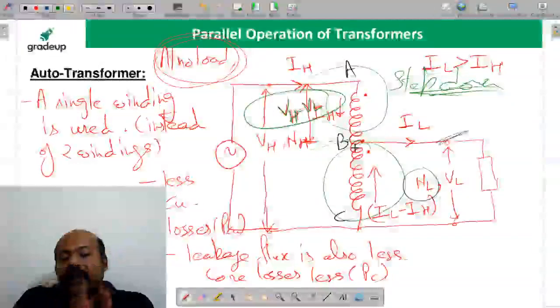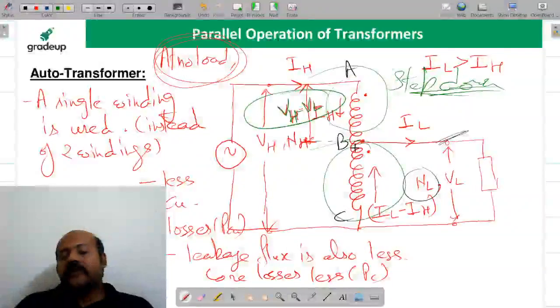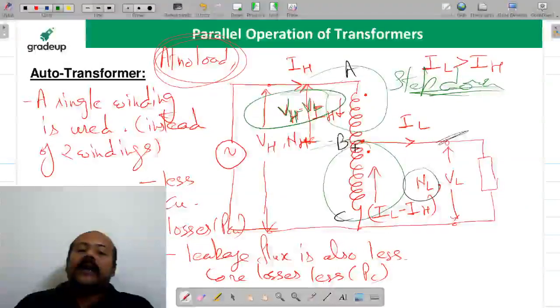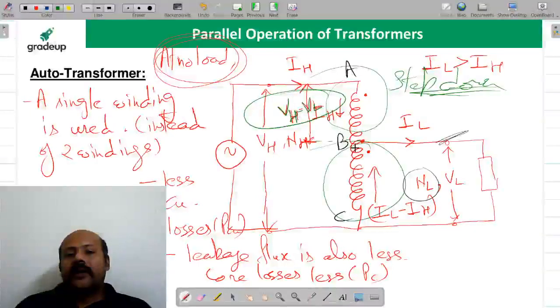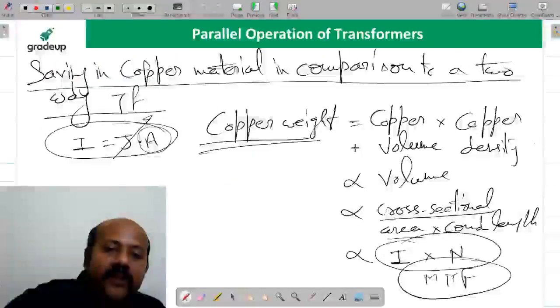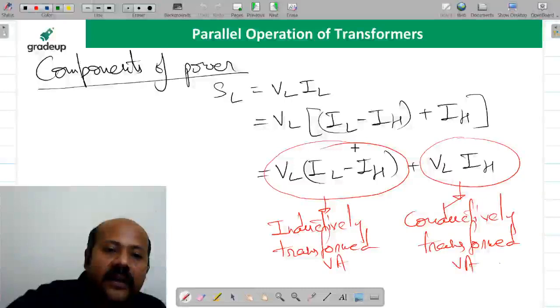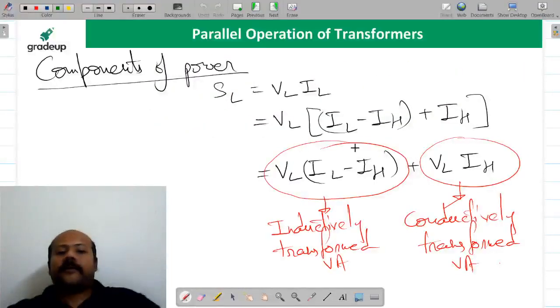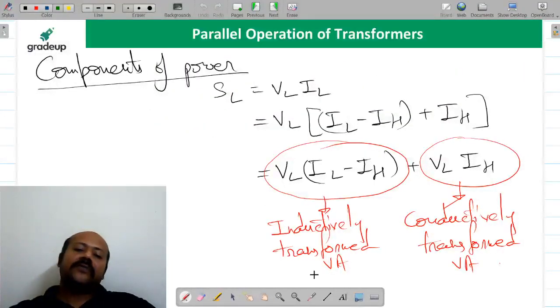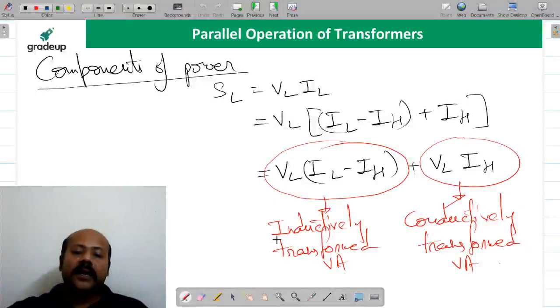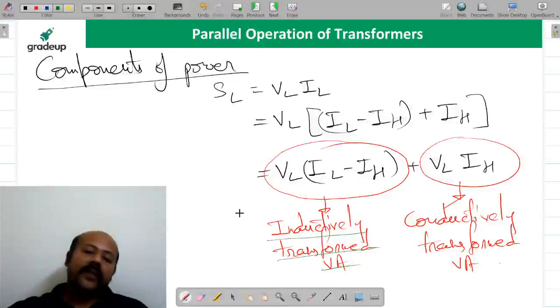And what is the method through which power is transformed in a two winding transformer? That is mutual induction. So this part of the power, this component, we call the inductively transformed power, for the BC section of the winding. It means your auto transformer is actually transferring power in two components. One component is the inductively transformed VA, which is because of the transformer action.